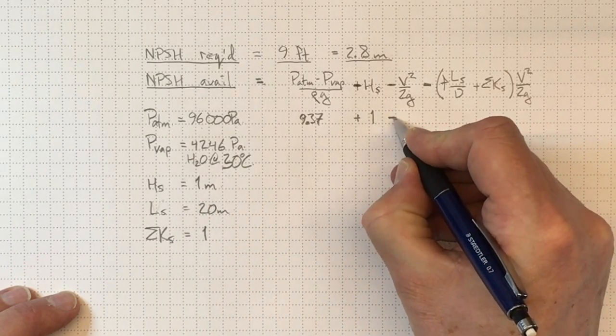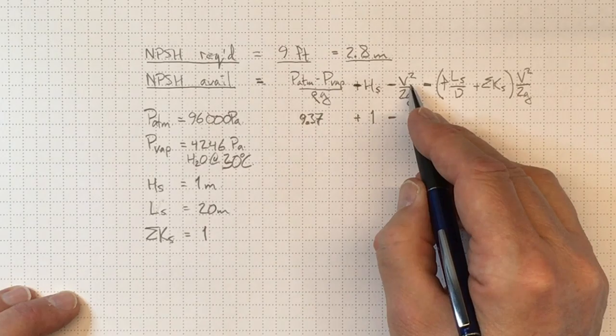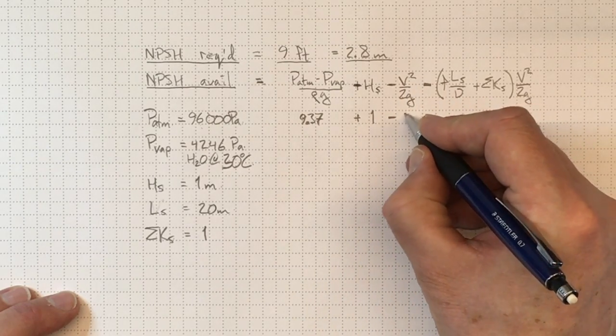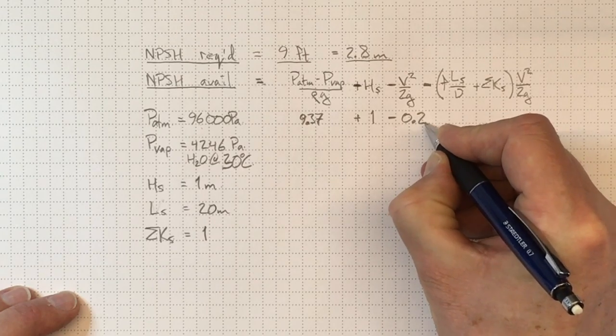We're actually increasing that by one because of the system head available, and then we have to take into account the fact that we're going to drop by V squared over 2G, and the velocity is fairly low, so the V squared over 2G is going to wind up being around 0.2.